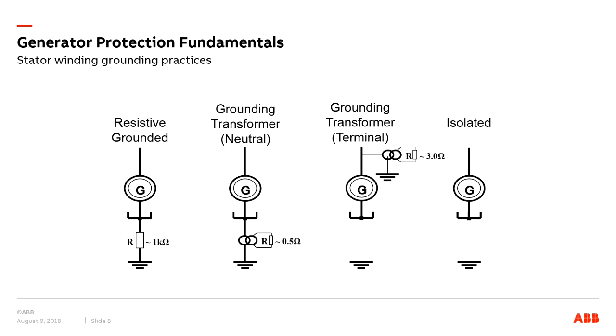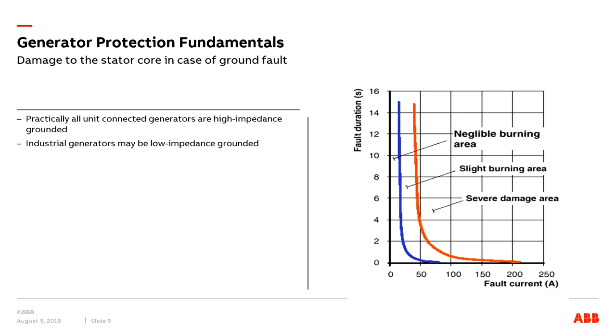And the other method is with no intentional grounding of the generator stator winding. So you can see there is no physical connection here. The only grounding path is the natural capacitance of the generator stator winding. And there are some problems with this kind of arrangement with the small winding capacitances, ferroresonance, and high transient overvoltages in case of ground fault. So practically, all unit connected generators are high impedance grounded generators.